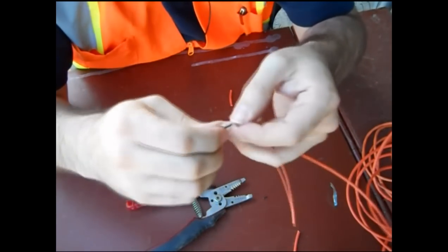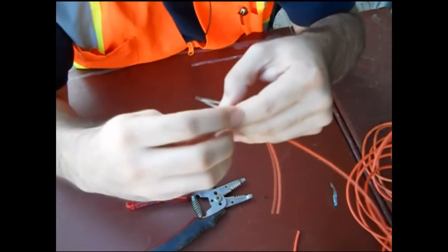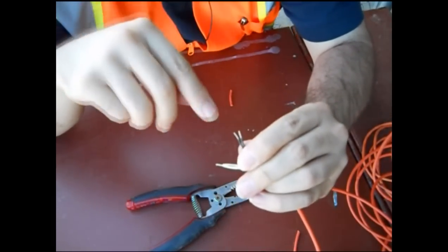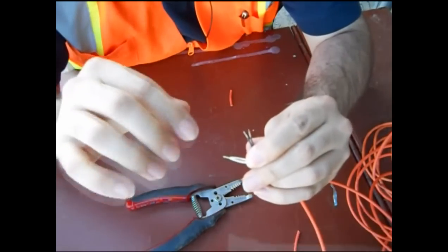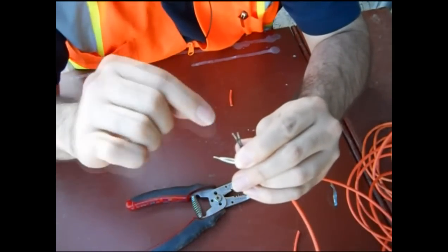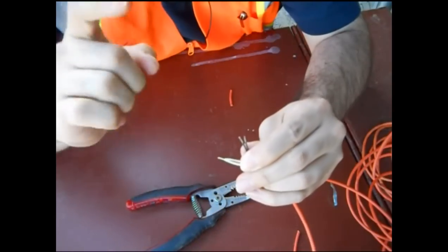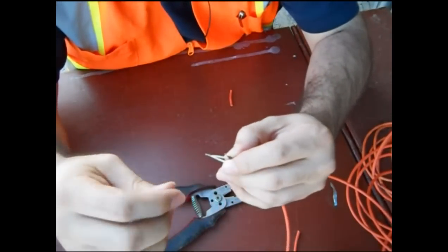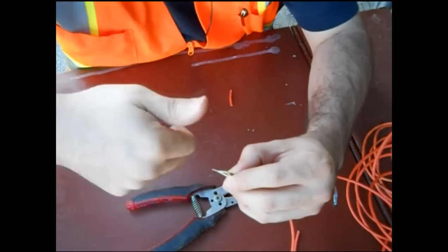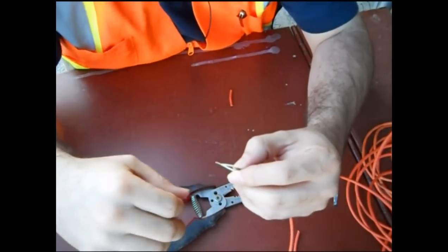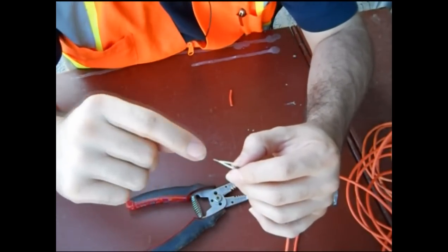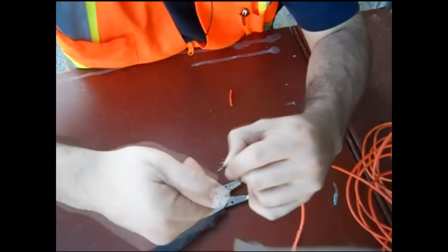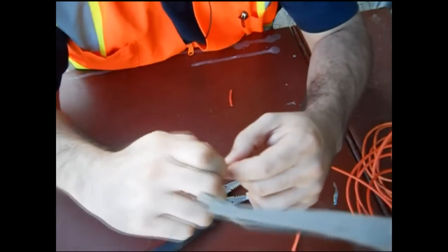If you're used to listening to electricians they'll always tell you you put the two wires together and then shove them into the wire nut. I say not to do that with stranded because it doesn't always work on stranded. With solid copper which is what electricians always work with that works great. Grab two solid copper conductors side by side like that, shove a wire nut on there and start wrenching it down, works perfect. But you don't want to do that with stranded. You always want to go ahead and twist them first. So control freak says twist them first. Tell anyone that asks you.